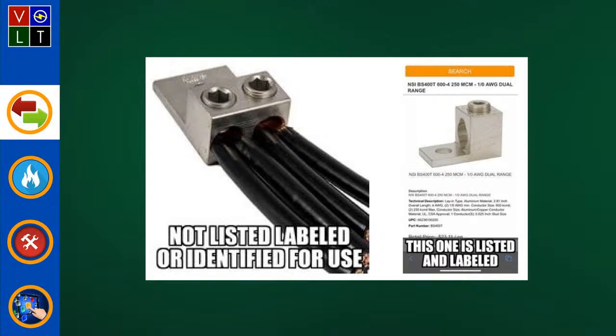It was my idea actually, because I was like, well, you got this lug that's listed for parallel conductors, can we just parallel the number 6 up there? They went and looked at it and said yeah, that's the only way you could do it. So we torqued it real good and got all our listed torquing marks. Out there they do torque witness, so we have to sit there and torque it with the guy witnessing us, then we sign off on the torque values and measure everything. It's crazy out there, nothing's gonna really mess up in the patch because they're so thorough when it comes to torquing and using the right materials, listing and labeling, all that stuff's really scrutinized out there.